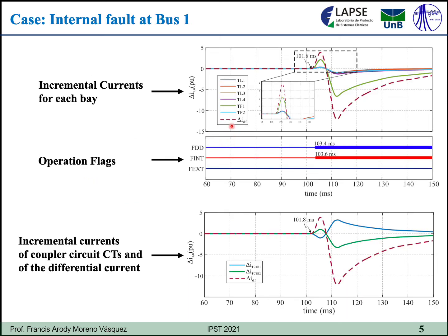First, I have an internal fault at bus 1, and we can see that all of the incremental currents and the differential incremental current have the same polarity. The fault occurs at this instant, and the internal fault is identified in less than 2 milliseconds. Also, we can notice that the differential incremental current has the same polarity as the current transformer CT1B2, which is connected to bus 2, but it measures the currents entering bus 1.